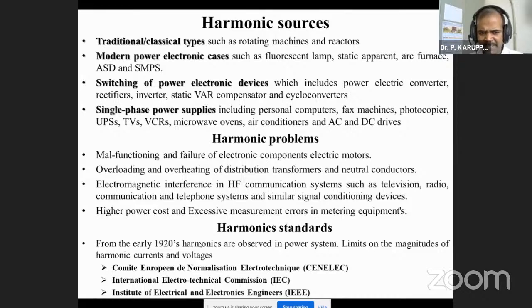Harmonics also cause malfunctioning and failure of electronic components and electric motors. Most home appliance motors are given 5 years warranty; nowadays some come with a 10 year compressor guarantee. However, if you want to increase the lifetime of electronic components, we should address the harmonic problems.